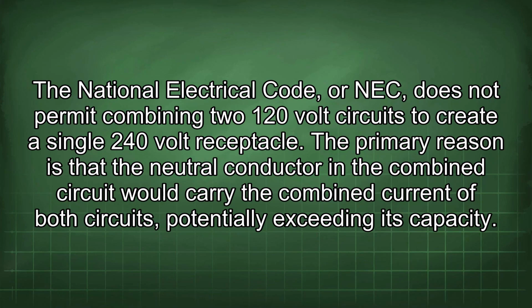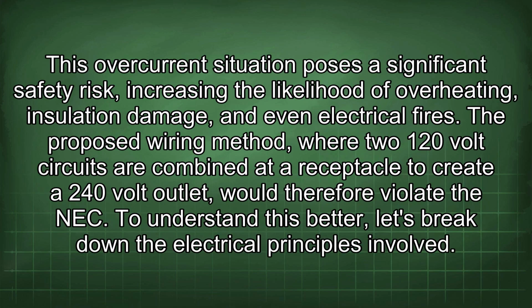The National Electrical Code, or NEC, does not permit combining two 120-volt circuits to create a single 240-volt receptacle. The primary reason is that the neutral conductor in the combined circuit would carry the combined current of both circuits, potentially exceeding its capacity. This overcurrent situation poses a significant safety risk, increasing the likelihood of overheating, insulation damage, and even electrical fires. The proposed wiring method, where two 120-volt circuits are combined at a receptacle to create a 240-volt outlet, would therefore violate the NEC.